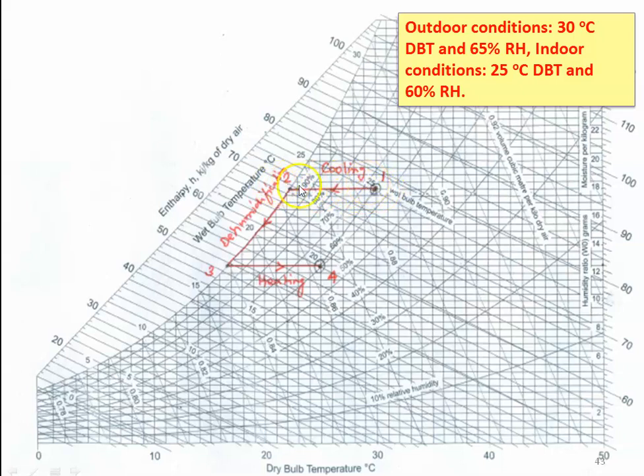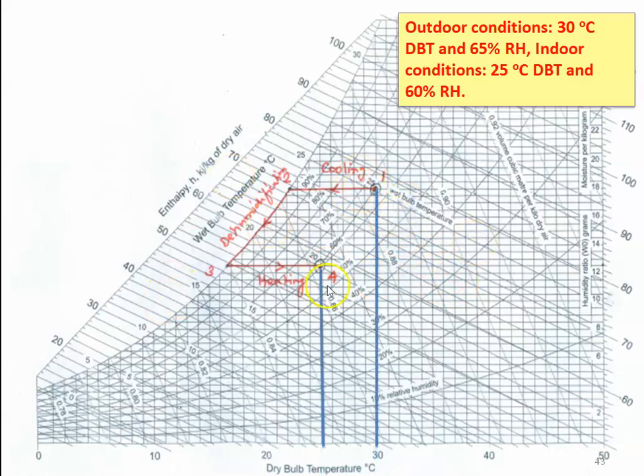How is this achieved? First there will be sensible cooling to reduce the temperature to the saturation temperature. Once the air reaches saturation temperature and you further cool, there will be dehumidification — water vapor is removed. This occurs in the dehumidifier. Then we heat the air again to achieve the required indoor condition. So the process is: 1 to 2 is cooling, 2 to 3 is dehumidification, and 3 to 4 is heating.